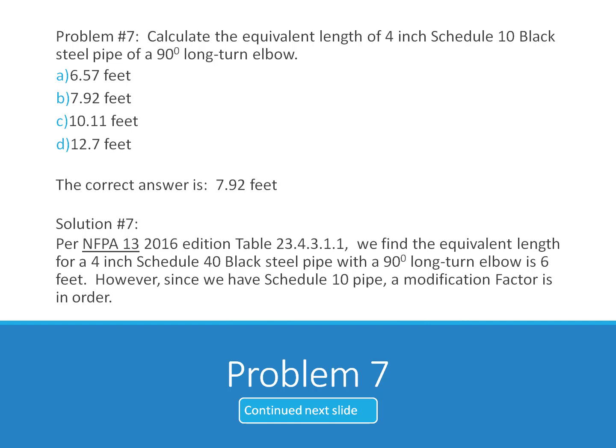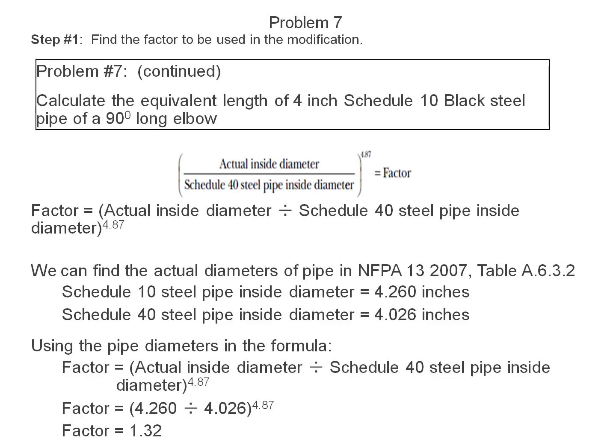The solution, per NFPA 13, 2016 edition, Table 23.4.3.1.1. We find the equivalent length for a 4 inch Schedule 40 black steel pipe with a 90 degree long turn elbow is 6 feet. However, since we have Schedule 10 pipe, a modification factor is in order.